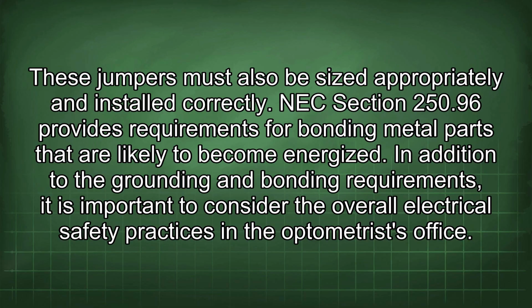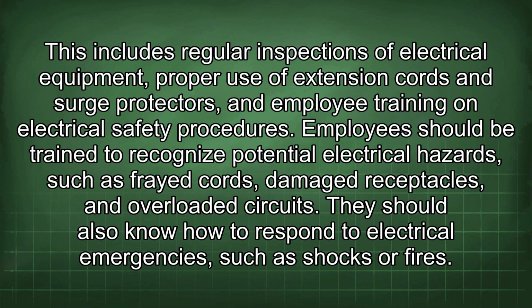NEC Section 250.96 provides requirements for bonding metal parts that are likely to become energized. In addition to the grounding and bonding requirements, it is important to consider the overall electrical safety practices in the optometrist's office. This includes regular inspections of electrical equipment, proper use of extension cords and surge protectors, and employee training on electrical safety procedures. Employees should be trained to recognize potential electrical hazards such as frayed cords, damaged receptacles, and overloaded circuits. They should also know how to respond to electrical emergencies, such as shocks or fires.